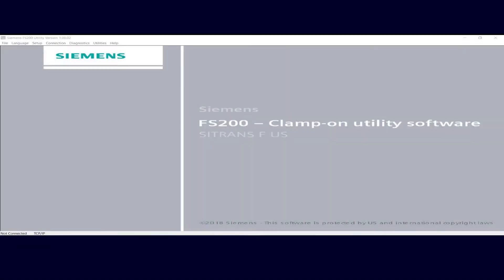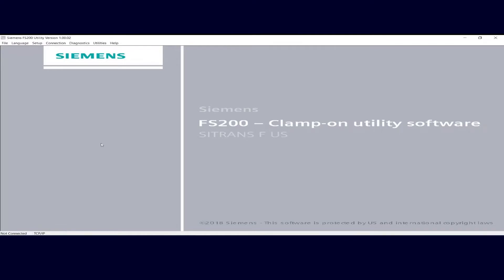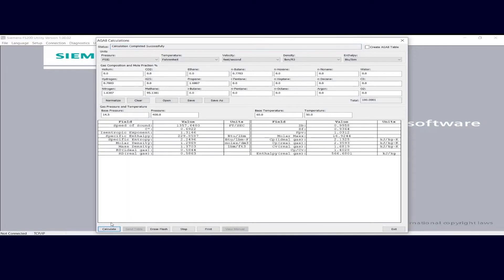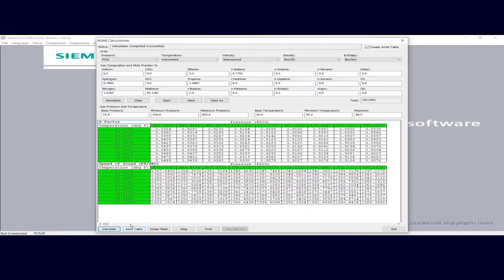Hi again everyone, John Accardo here. Welcome to part 3 of this series covering the FS200 Clamp-On Utility software. In today's session we're going to discuss the AGA-8 calculations capability of the tool. The FS200 Utilities AGA-8 calculations tool allows you to perform enthalpy calculations for your gas and also enables creation of an AGA-8 table that you can upload to your FS230 flow meter to enable standard volume calculations for fixed gas compositions without the need for a flow computer.